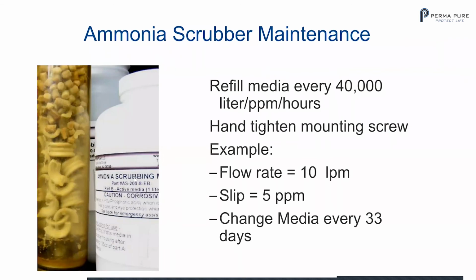So here's your ammonia scrubber maintenance. We refill media every 40,000 liter ppm hours. So that's the capacity of one ammonia scrubber, 40,000 liter ppm hours. So we can calculate that at a flow rate of 10 liters per minute, with a slip of 5 parts per million, we change media every 33 days. Fortunately, we have customers with such a huge amount of ammonia that they have to change the media every couple days.